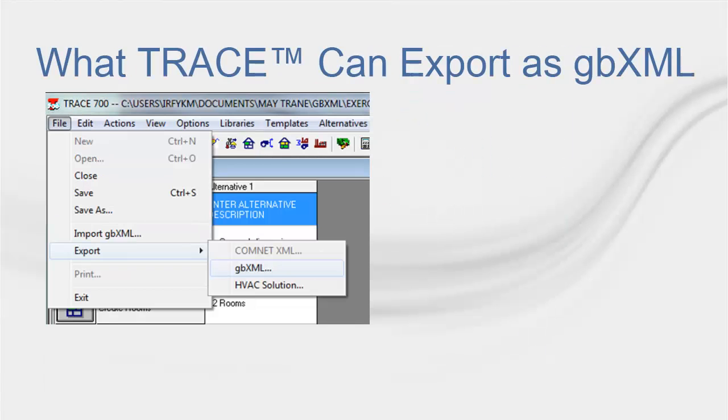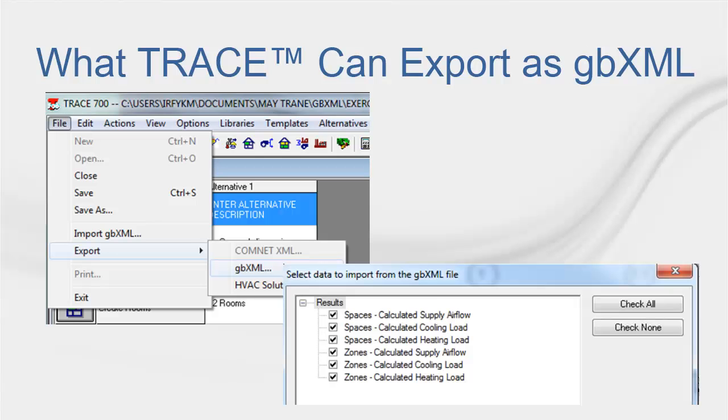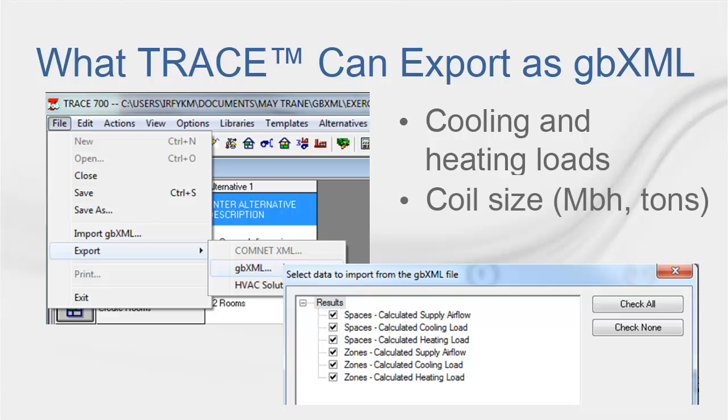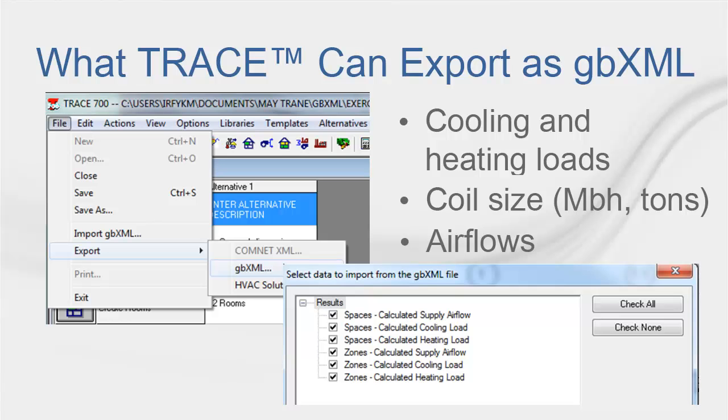After the simulation has been calculated, the file can be exported from Trace as a GBXML file to then import it into the CAD program, and the design information will be transferred with it. The load design information that can be exported includes space or zone heating and cooling loads, coil sizes, and air flows. This Export GBXML feature exports design information only to an existing XML file that was used to create the current Trace file. The feature will be grayed out if the file has not been calculated.